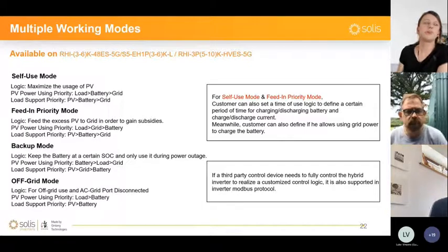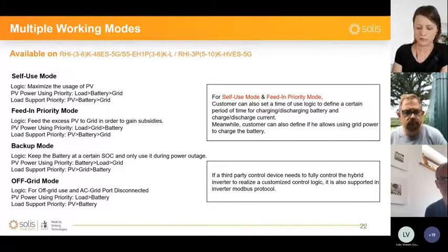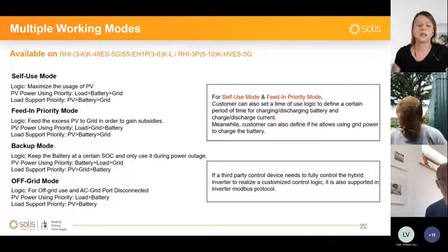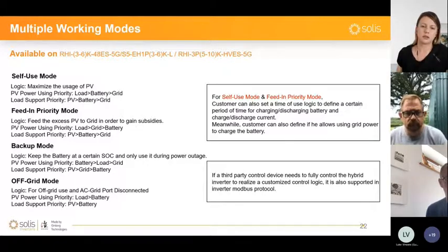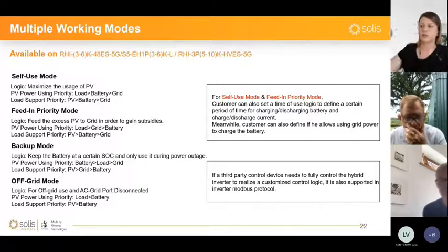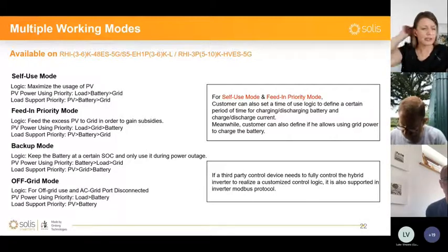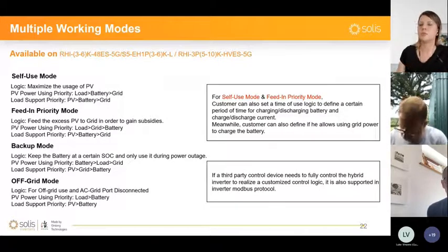The third one is the backup mode. The backup mode is very useful for systems which are installed in areas where the grid might be very unstable. What the customer has here is the option to keep the battery at a certain limit, a certain state of charge. For example, they can choose to always have the battery topped at 50% when there is a grid connection available. So it will not be discharged into the loads under 50%. And in case of an outage, that 50% will become available in order to supply those critical loads.